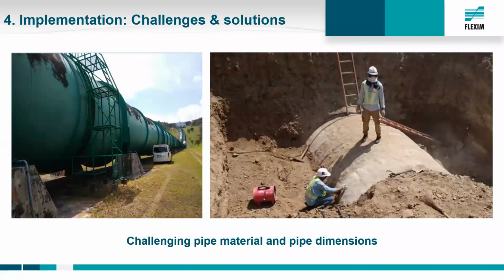Coming to another challenge, which is typical for the water industry, is that we are facing a very huge variety of pipe materials and pipe dimensions. Here we can see a big water supply line on the left in Southeast Asia, and the right one is as well located in Southeast Asia. Big water supply lines with challenging material, PCCP, on the right side. And so we have a huge variety of wall thicknesses and pipe outer diameters and materials, which can challenge the ultrasonic non-invasive flow measurement technology.